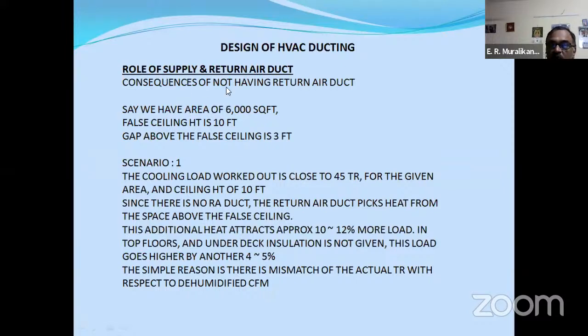Now, I explained the consequences of not having a return duct. Say we have a 6,000 square feet area, the false ceiling is at 10 feet, and the gap above the false ceiling is 3 feet. The cooling load works out close to 45 TR for the given area and ceiling height of 10 feet. Since there is no return air duct, the return air picks up heat from the space above the false ceiling. This additional heat attracts approximately 10 to 12% more load. On top floors and under deck insulation is not given, this load goes higher by another 4 to 5%. That is, instead of 10, it will be roughly 15%, especially in daytime in peak summers. The simple reason is the mismatch of actual TR with respect to the dehumidified CFM. Say for dehumidified CFM you want 10,000 CFM, but because of the additional load, there is starvation of the cooling effect.